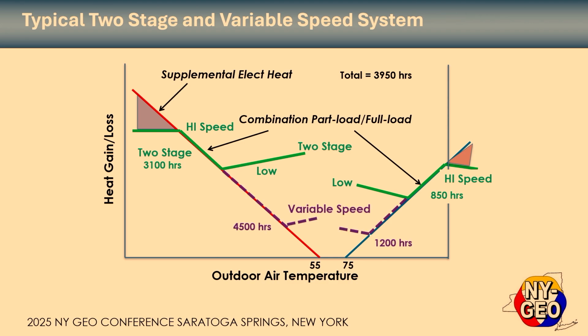And then we'll see here that as we add the variation of variable speed, of course you can see that it's a much lower capacity. Usually the turn down is at least 4 or 5 times, so you're getting into 20-25% capacity. And you can see that you can do the very same thing and track the load most of the time. This is why variable speed equipment runs a fair amount longer than single speed or dual capacity, because you're running at a much lower capacity but a lot longer. It typically results in a very comfortable home, and also lower RPM generally means higher efficiency. So variable speed gives you that benefit.